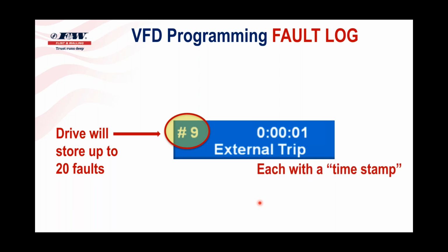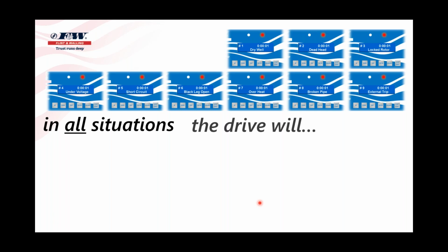But another cool thing is they all will come with a timestamp. And that timestamp's going to read in hours or days, hours, and minutes. So, for example, I could look at this. I could see it's the 9th fault of this drive, and it happened a minute ago, where it had an external trip. So that's kind of a cool little feature to it as well. But I will tell you this, and I'm winding down here. Most of these don't take a whole hour to complete.